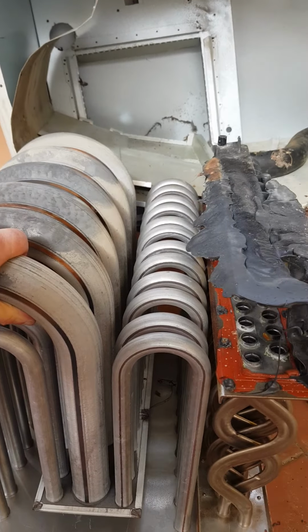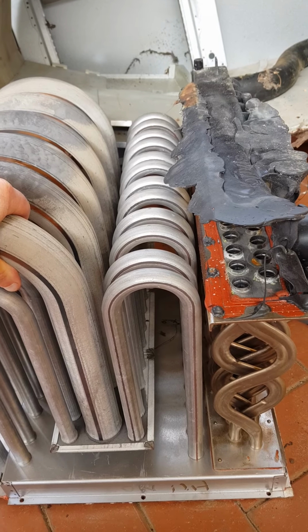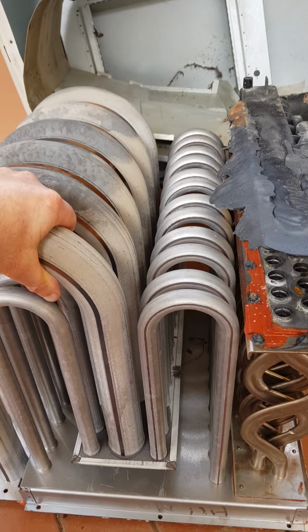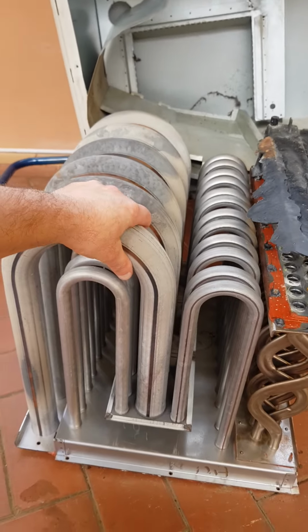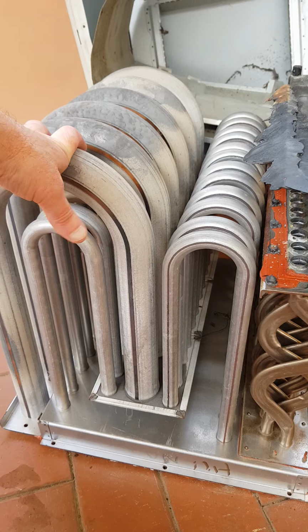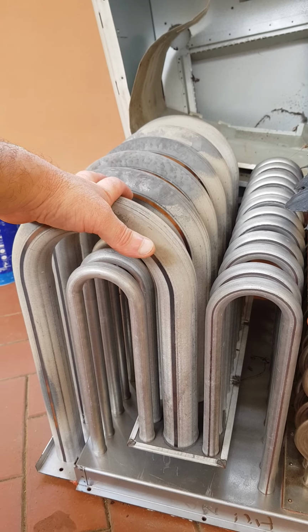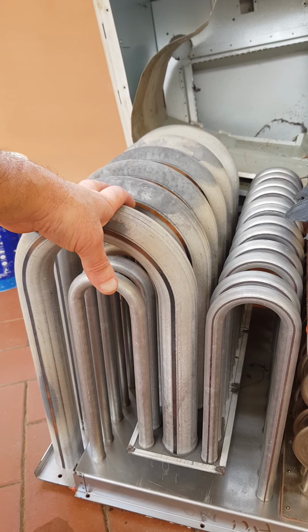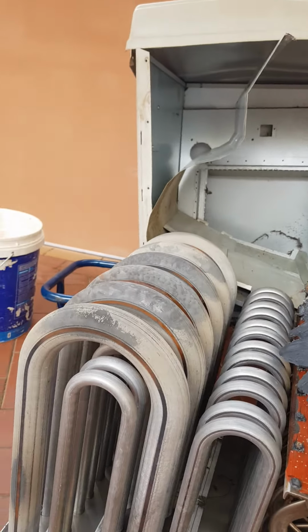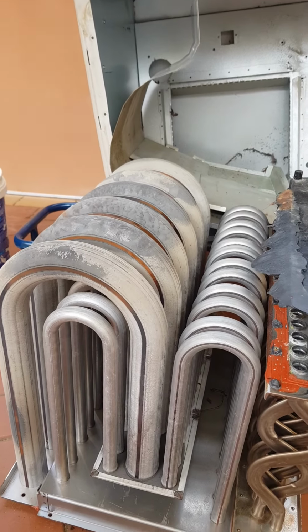Now, in this particular model, to service or to see this heat exchange, the unit must be dismantled. Now, this is an external unit, which makes it a little bit easier, but there are no service panels, and to service it you must dismantle the actual heater. So for a lousy odd $200, a service repairman will not do this. I'm not saying all of them won't do it, but the majority will not dismantle this heater.